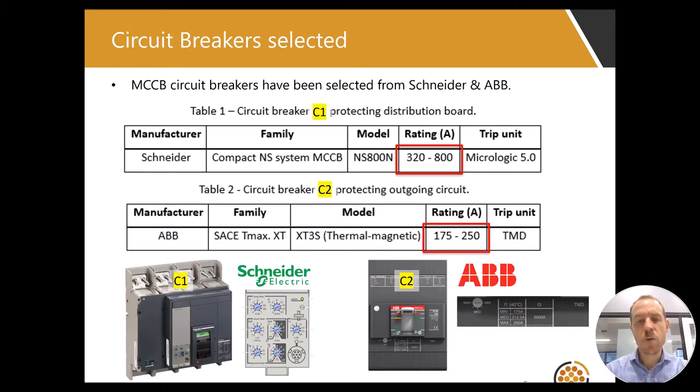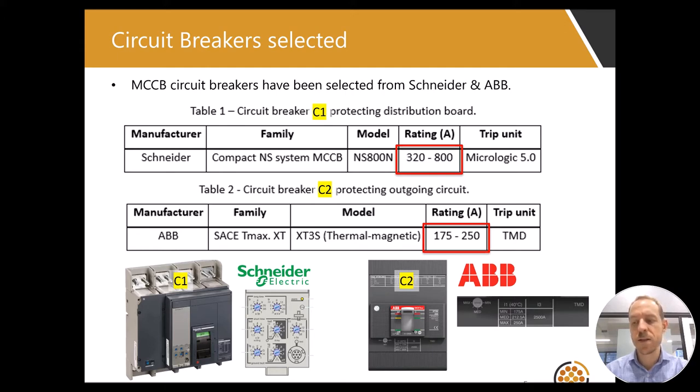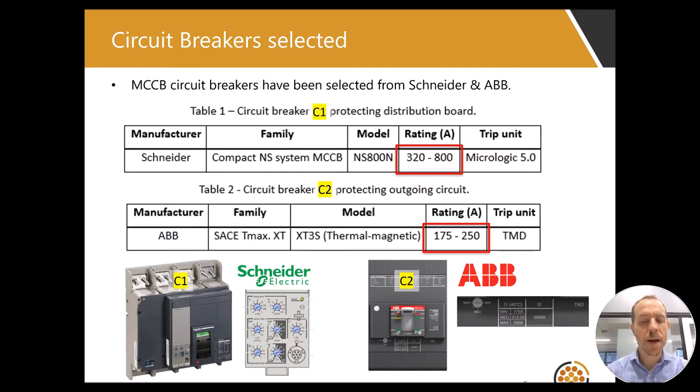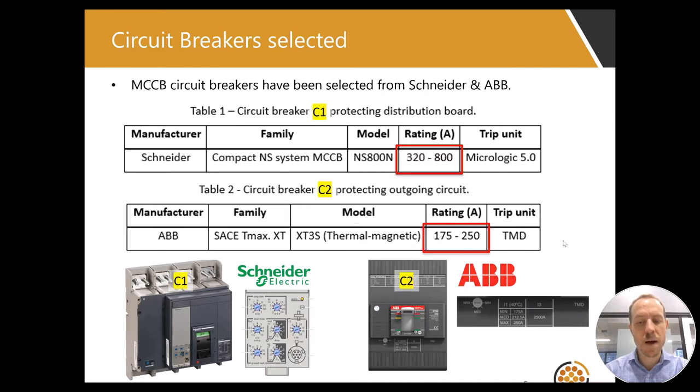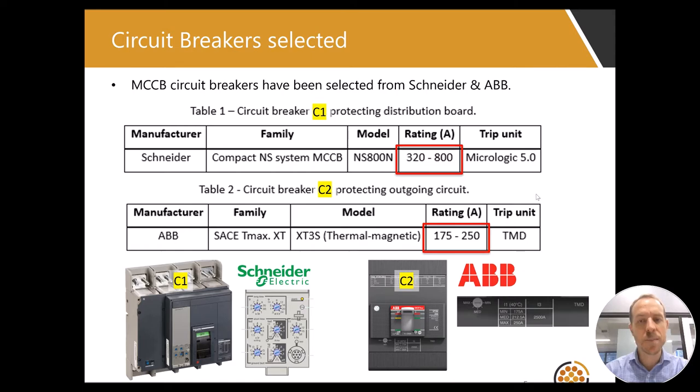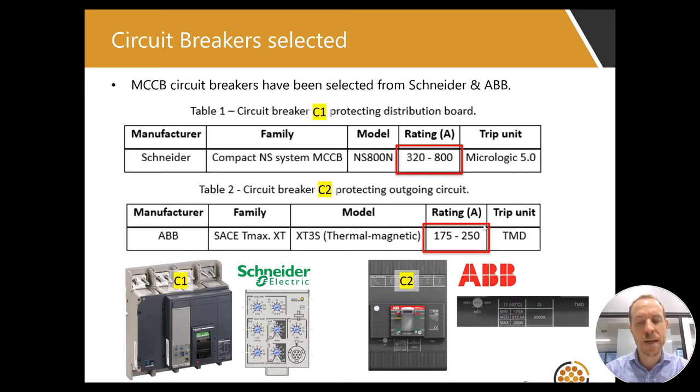Now we will select the circuit breaker types and ratings. Both C1 and C2 will be MCCB type, with ratings to match the load currents. C1 will be a Schneider electronic type with micrologic trip unit, rated up to 800 amps. And C2 will be an ABB thermal magnetic type MCCB, rated up to 250 amps.